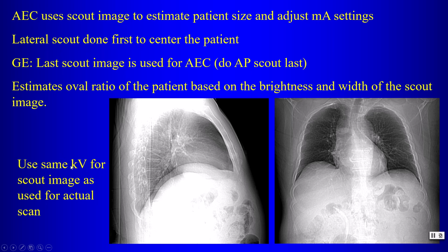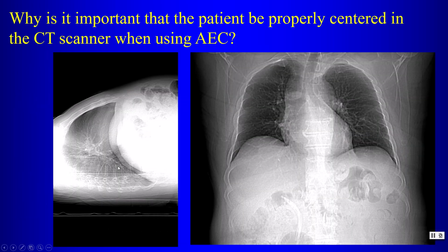So it's important to use the same kV for the scout image as used for the actual scan, since the calculations for automatic exposure control make that assumption.